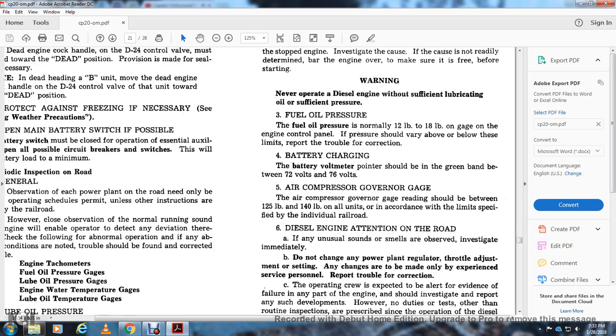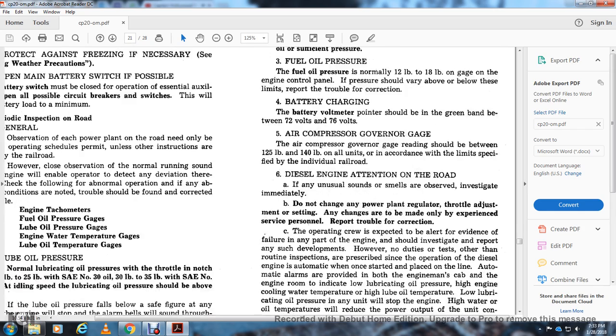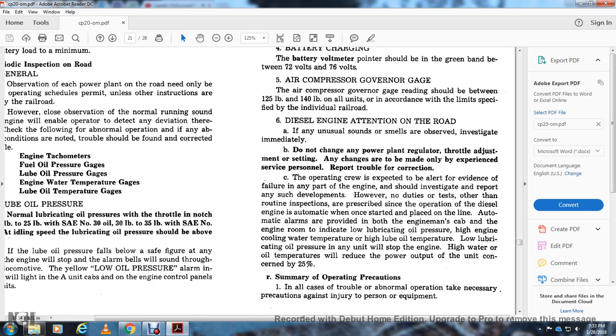Diesel engine attention on the road: if any unusual sound or smell is observed, investigate immediately. Do not change any of the power plant regulator or throttle adjusting settings. If any change is needed, only experienced service personnel should make it; report the trouble for correction. The operating crew is expected to be alert, and in the event of the failure of any part of the engine should investigate and report any such developments.